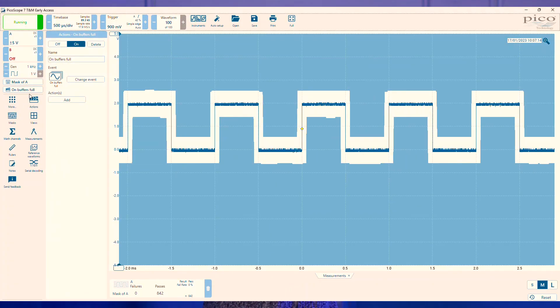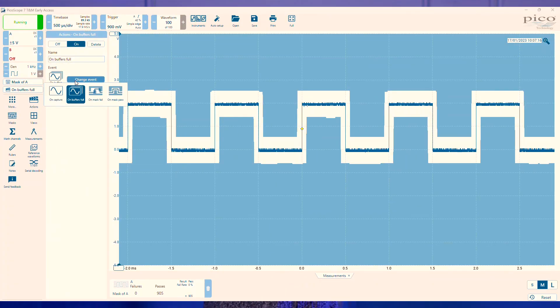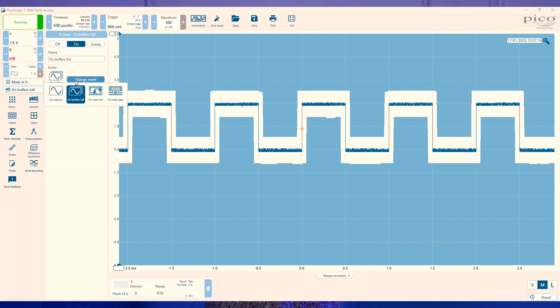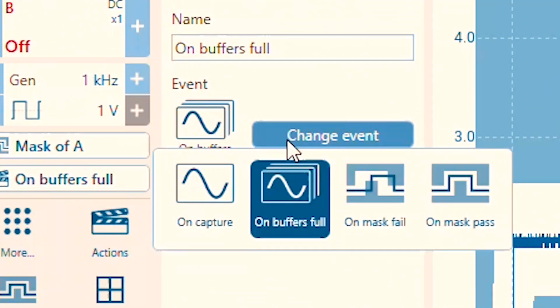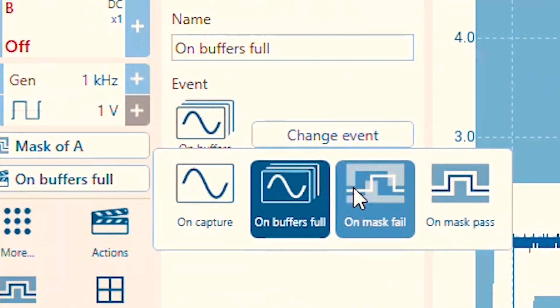Now if we want to do more than just display these failed captures, we'll need to use our actions. Actions allows you to make PicoScope 7 do something when a certain event happens. This event could be single capture, a full buffer, or a mask pass or fail.